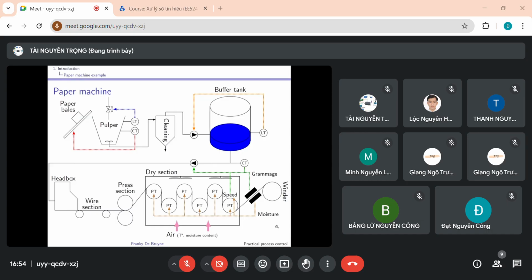In this paper process, there are also coupling effects between moisture and grammage. For instance, if you control moisture using speed, this is when the drying capacity is limited, as we are seeing, you can see that the grammage is also influenced by this speed change. But in this case, since we have implemented a feed forward, this coupling effect will be mitigated by this feed forward. When the grammage is adapted using a change in stock flow, as shown over here, this stock flow change also has an influence on the moisture content.